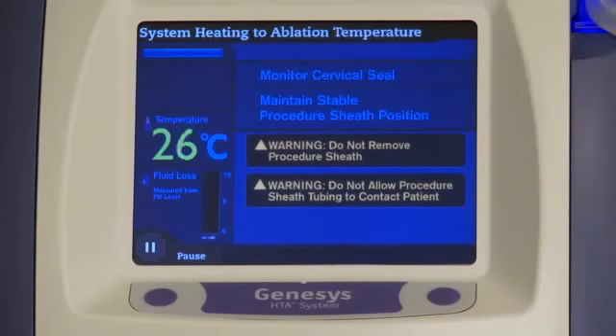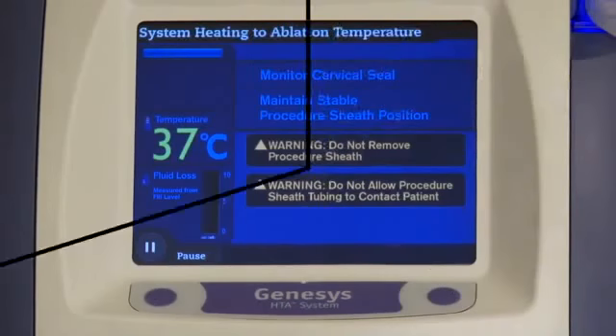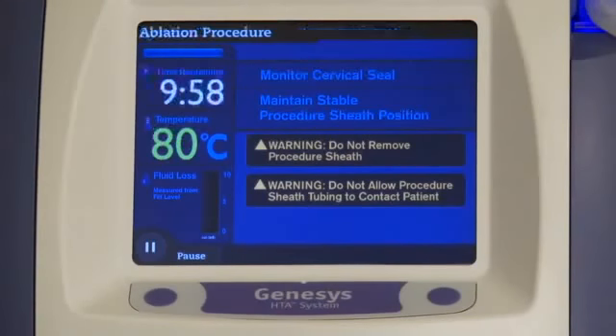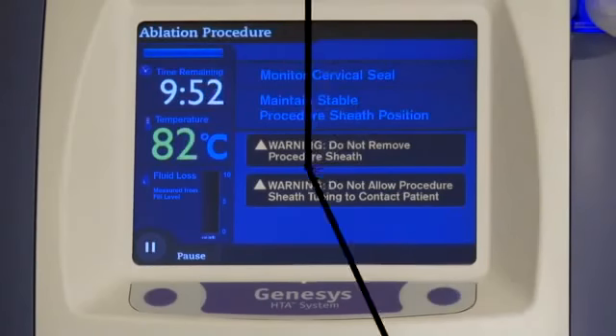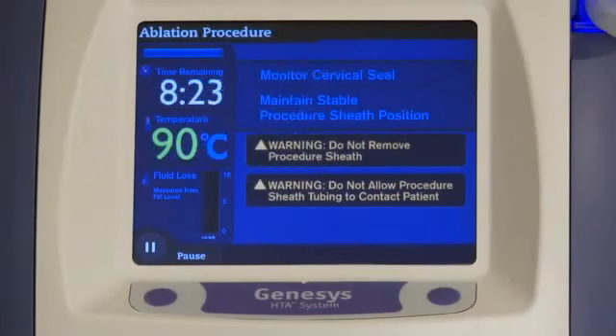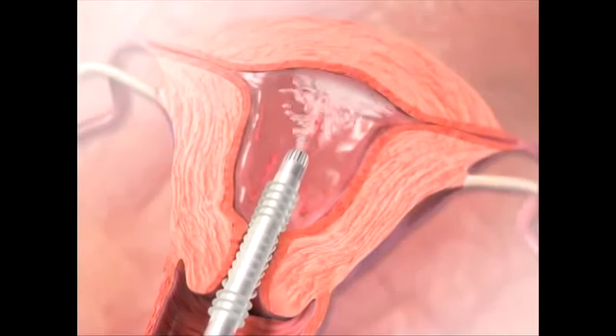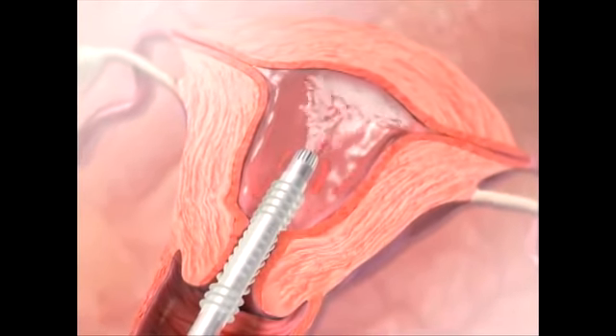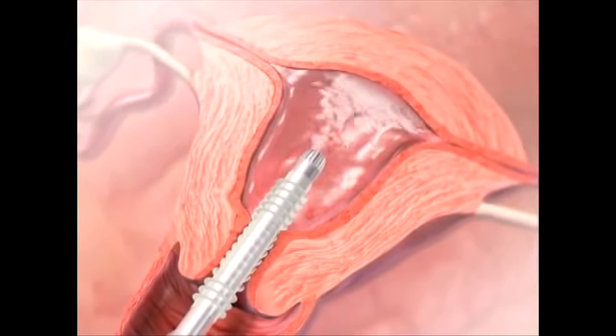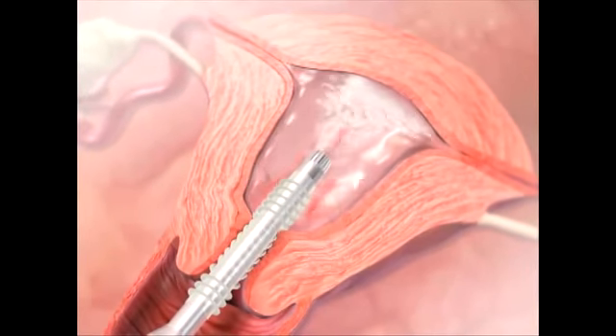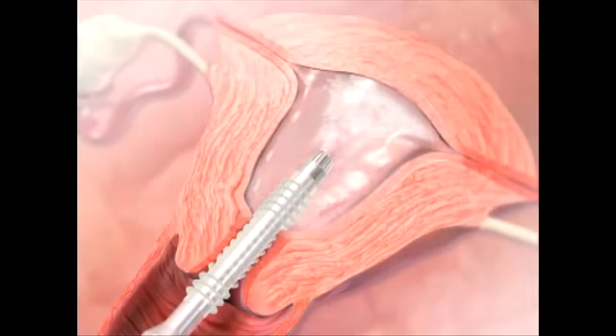Once heating has begun, it is important to maintain a stable sheath position. Throughout the heat-up and ablation phases, fluid level and fluid temperature are updated on the screen. When the fluid reaches 80 degrees centigrade, a chime will sound and the 10-minute ablation timer will be displayed. During ablation, the fluid temperature continues to rise to 90 degrees centigrade. The heated, free-flowing saline will conform to the uterine cavity, enabling the treatment of a variety of patients.